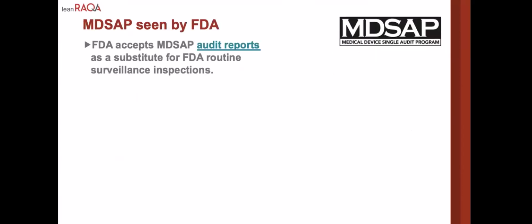So this is a significant difference. FDA accepts MDSAP audit reports as a substitute for FDA routine surveillance inspections. The report. So the audit organization actually is, whenever you get one of these MDSAP audits, they create a report and they send a copy of that report to each of the participating countries in which you're selling product. So the audit organization actually sends this directly to FDA themselves.